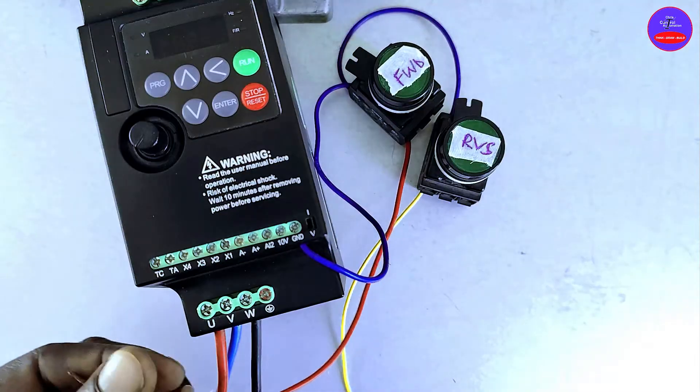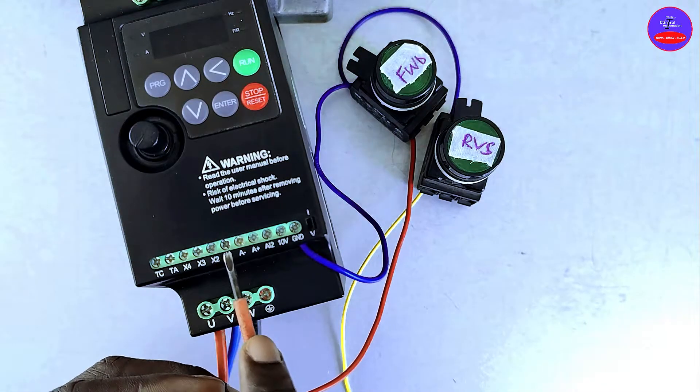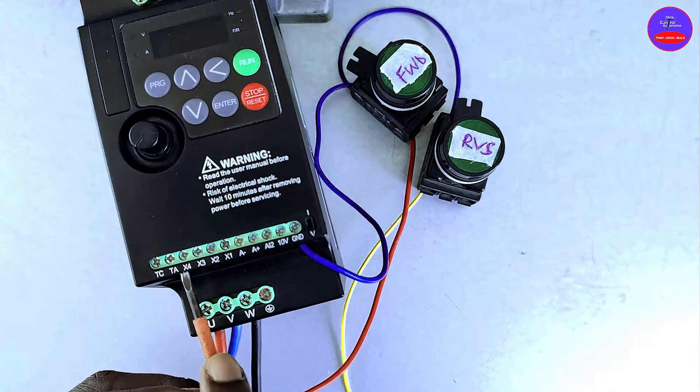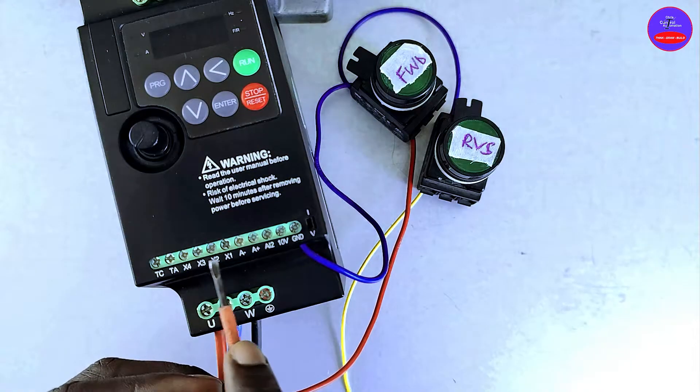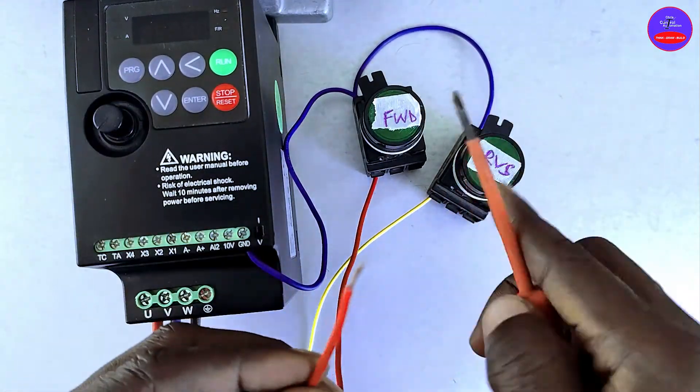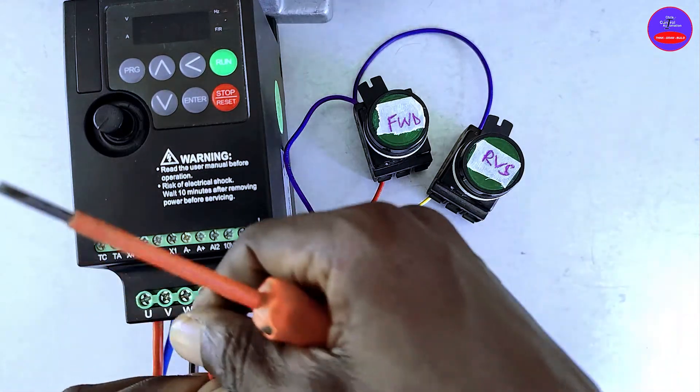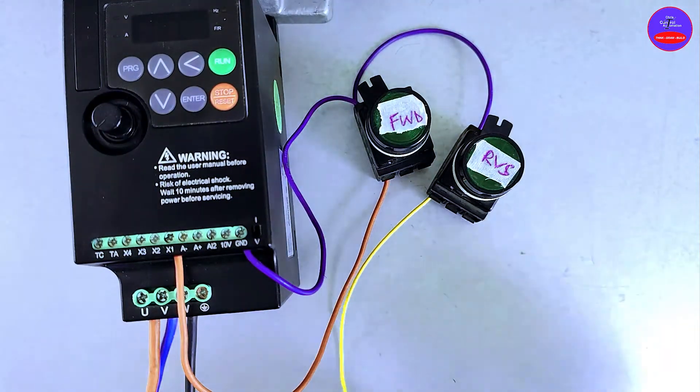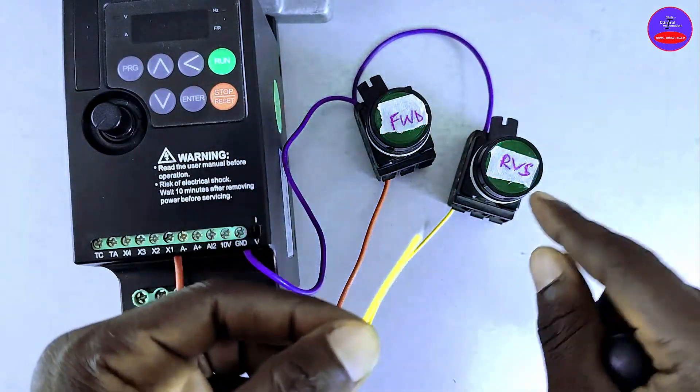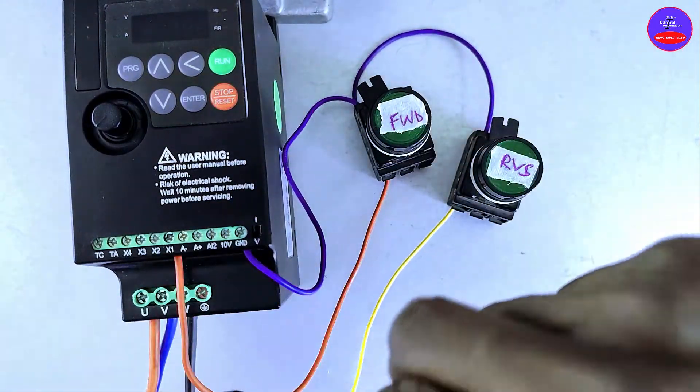We have control terminals X1, X2, X3, X4. We are going to use any two of these. The red cable from the forward push button will connect at X1. The yellow cable from the reverse button will connect at X2.